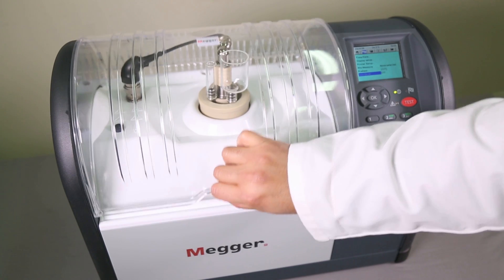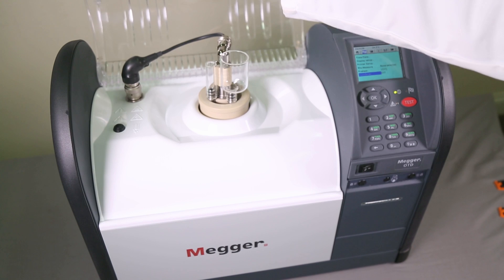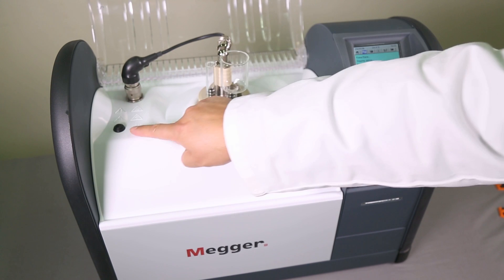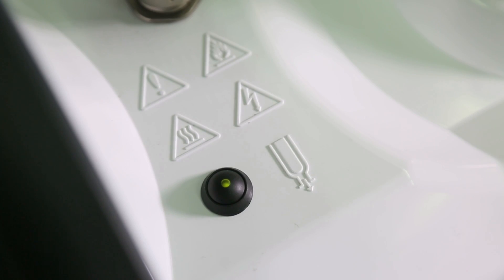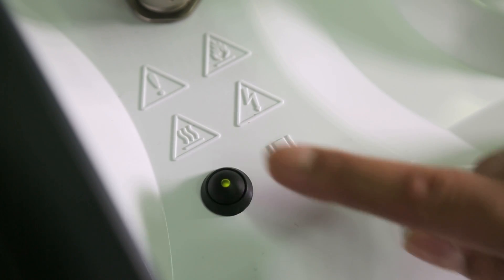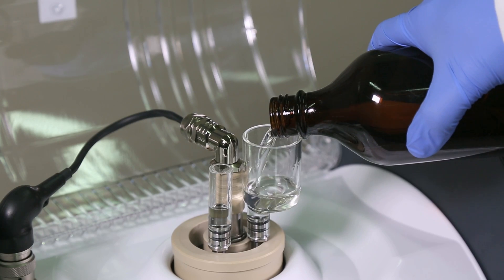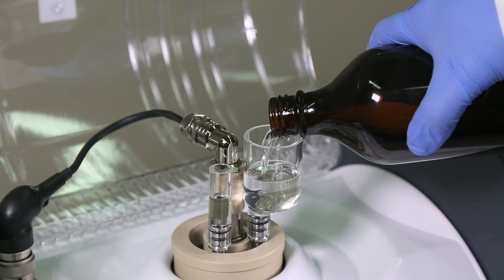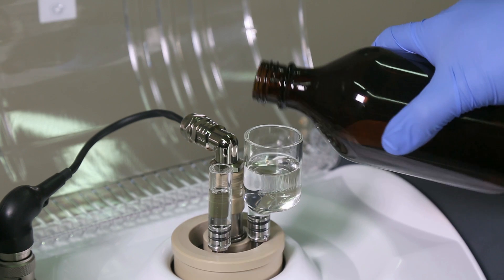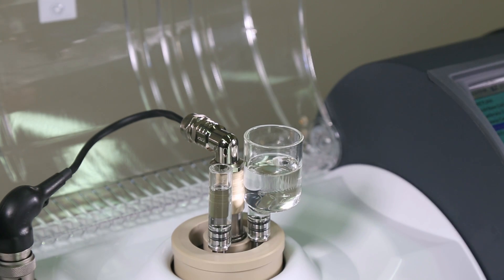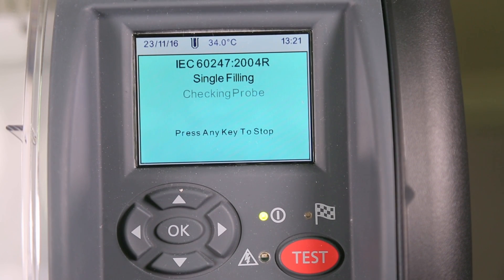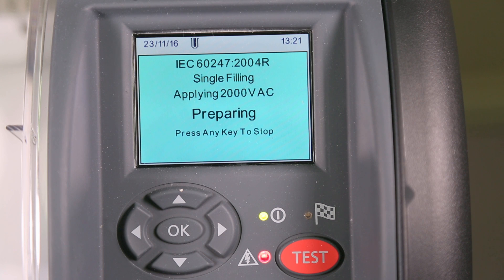Before starting the test, check that the oil drain valve is closed — a lit LED indicates it is open. Fill the test cell with your oil sample. Now press test. The OTD will run automatically for the entire test procedure.